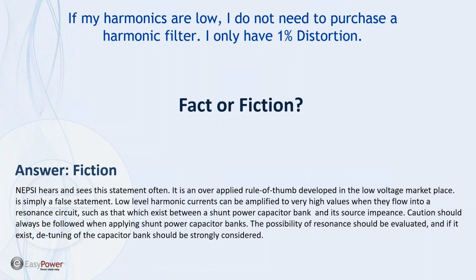Low-level harmonic currents can be amplified to very high values when they flow into resonant circuits, such as that which exists between a shunt power capacitor bank and its source impedance. So we so often hear a customer say, well, I only have 1 or 2% distortion, so I'm just going to install standard capacitor banks. This is just not the case. If you were to develop a very simple case in EasyPower, put a capacitor in the system and have it resonate with the source at the 5th harmonic and inject just 1 or 2 amps, you would see that the amplification can be significant enough to cause voltage distortion to exceed 5% and cause you to exceed IEEE 519 limits. So again, relatively low distortion does not make a difference.